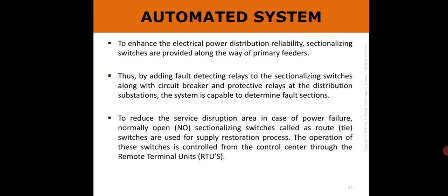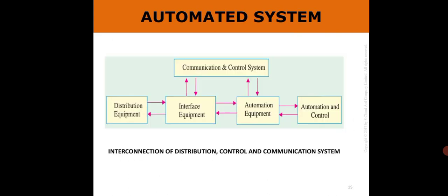Next, to reduce the service disruption areas in case of power failure, normally open sectionalizing switches, called tie switches, are used for the supply restoration process. The operation of these switches is controlled from the control center through the remote terminal units. This is the structure of the automated system.